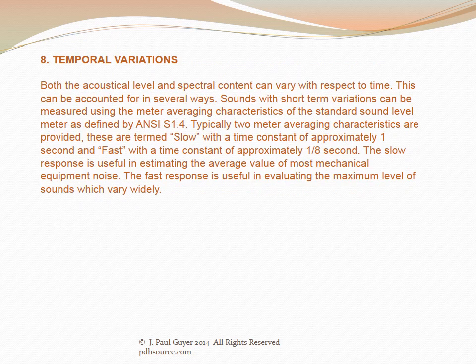Both the acoustical level and spectral content can vary with respect to time, which can be accounted for using the meter averaging characteristics of the standard sound level meter as defined by ANSI S1.4. Two averaging characteristics are provided: slow, with a time constant of approximately one second, useful for estimating the average value of most mechanical equipment noise; and fast, with a time constant of approximately one-eighth second, useful for evaluating the maximum level of sounds that vary widely.